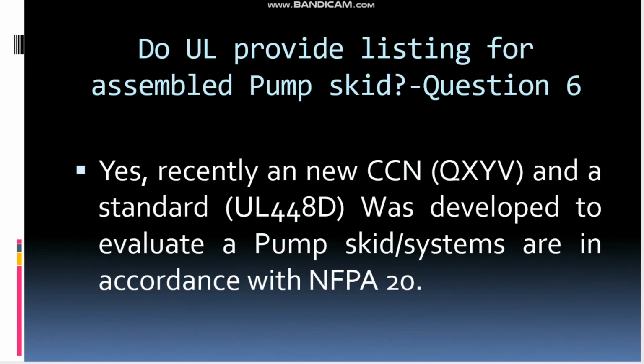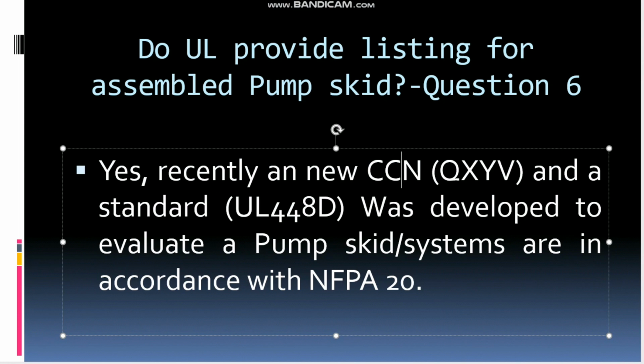Another UL question. Normally on site we receive the firefighting pumps separately: the electric pump, the diesel pump, and then the jockey pump or pressure maintenance pump. But there is another option: we can go with a skid type arrangement. So the question here is, does UL provide a listing for an assembled pump skid? The answer is yes. Recently a new CCN and a standard, UL 448D, was introduced. The D means the new. UL 448 is the old standard for stationary pumps. This was developed to evaluate pump skid systems in accordance with NFPA 20, so this is acceptable as per UL.